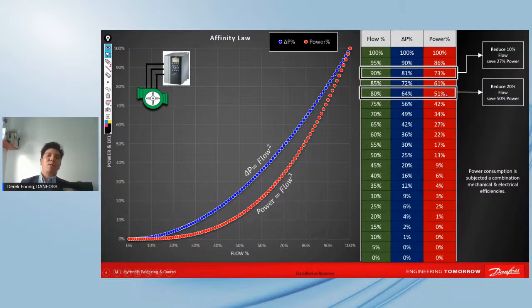So this is a very quick reference that you can see in the affinity law, without factoring in all the rest of the inefficiencies. If we want to be meticulous, then we would factor in all the mechanical inefficiencies in this equation. But we are looking at the surface right now, where it gives you a very quick estimation of how much flow rate reduction gives what savings. Of course, there are two curves right here. What I was mentioning is a result, and in between, you have differential pressure savings.